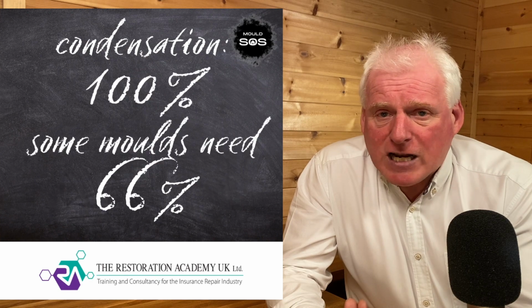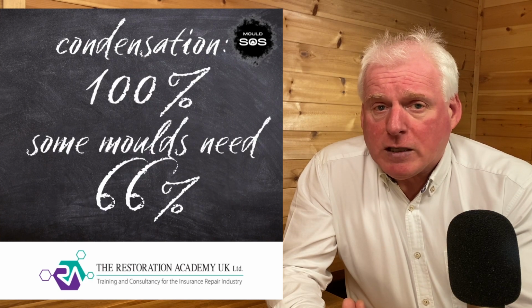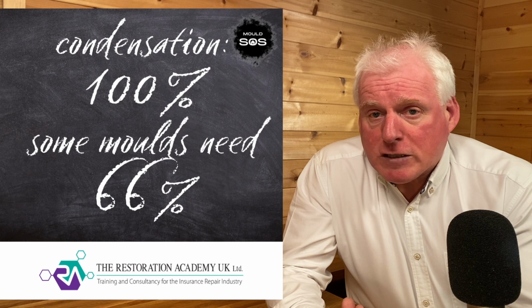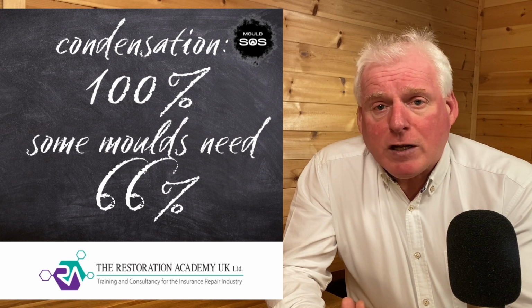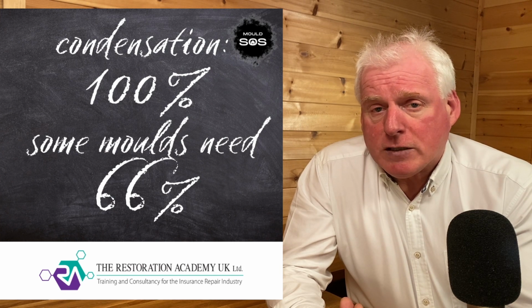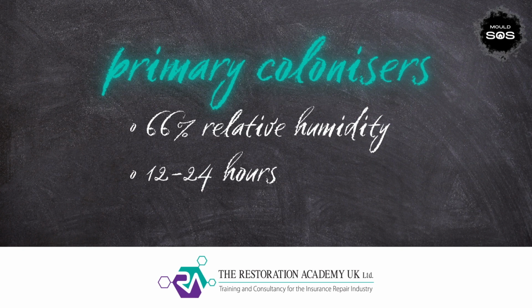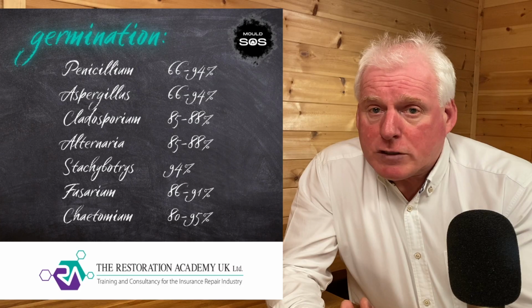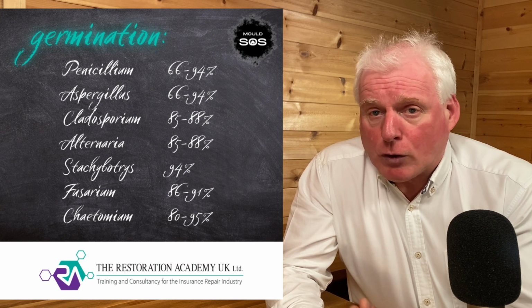But mould does not need 100% relative humidity to germinate and grow. Some species of mould will grow when they are exposed to a relative humidity as low as 66%. These are referred to as primary colonizers. These are the organisms whose evolutionary niche is to be the first to exploit the available food source. This slide shows types of mould and their germination requirements.